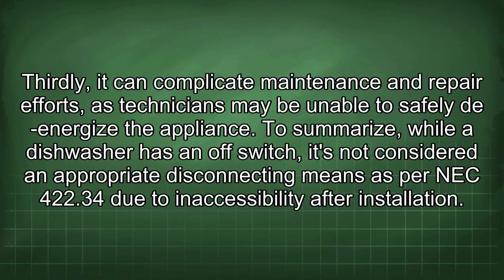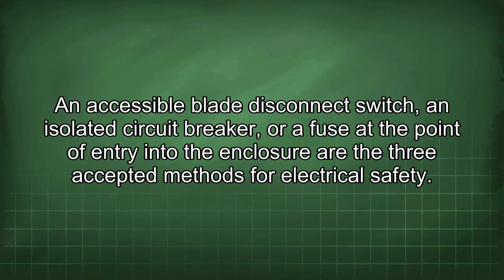To summarize, while a dishwasher has an off switch, it's not considered an appropriate disconnecting means as per NEC 422.34 due to inaccessibility after installation. An accessible blade disconnect switch, an isolated circuit breaker, or a fuse at the point of entry into the enclosure are the three accepted methods for electrical safety.